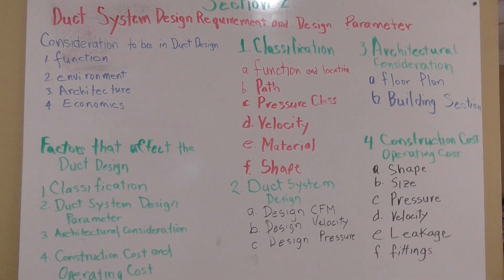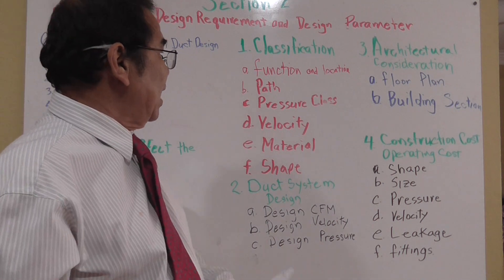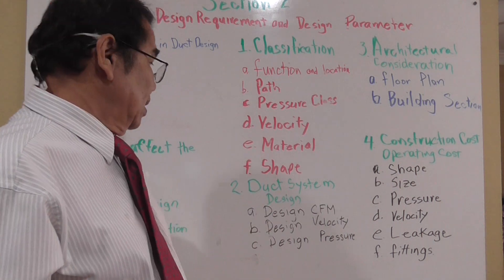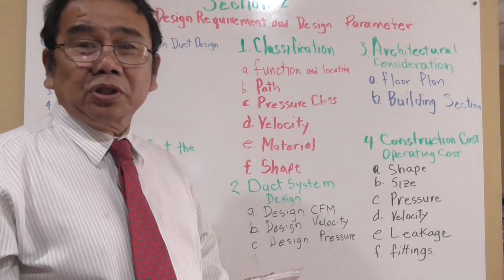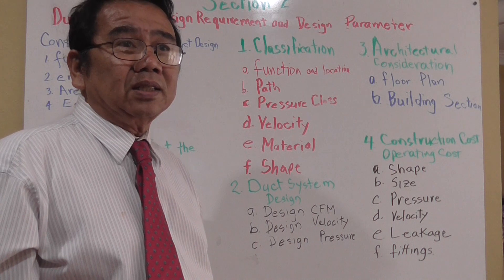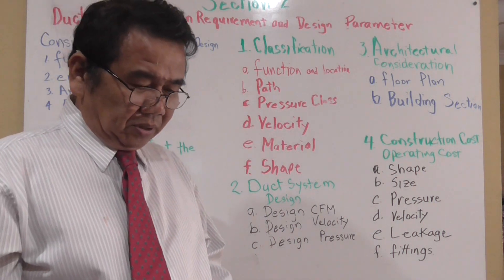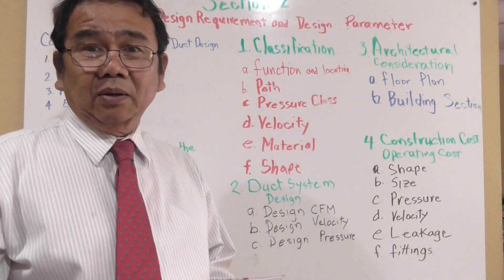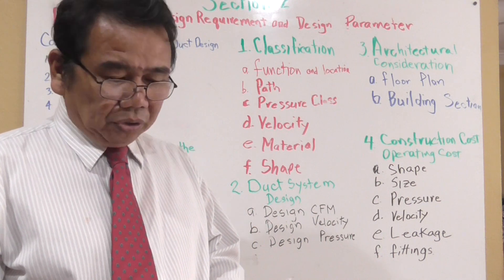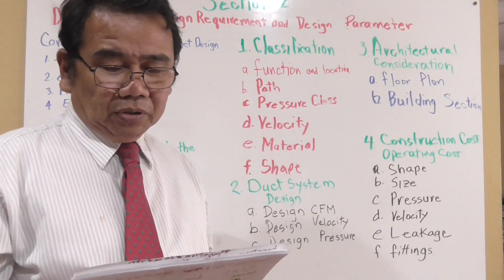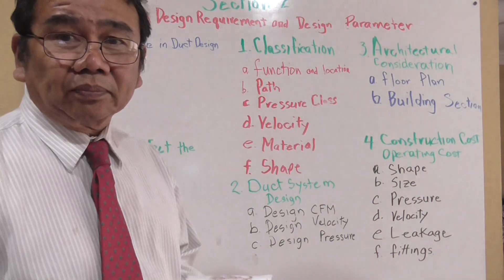On the classification part, we're gonna talk about the function and location, the pressure class, the velocity, the material, and the shape. On the function and location, environmental duct exposure must be considered — where the equipment or duct system is going to be located, inside or outside the building, whether it's negative or positive pressure, fumes and moisture, rust, corrosion, mold, and chemical reaction. The supply duct and exhaust duct are positive type ducts. Return and outdoor ducts are negative pressure ducts.